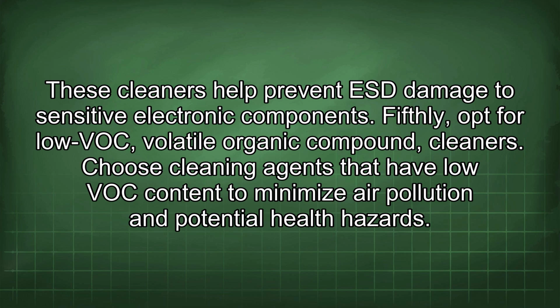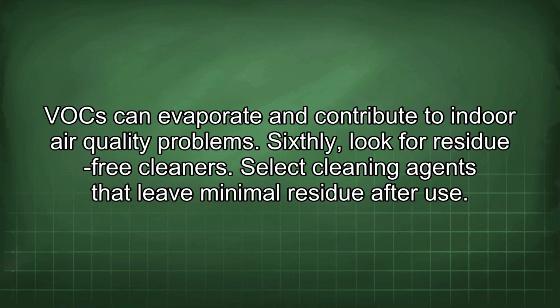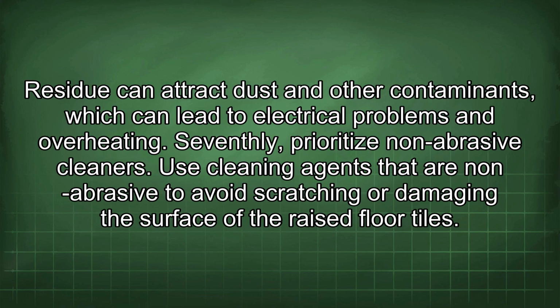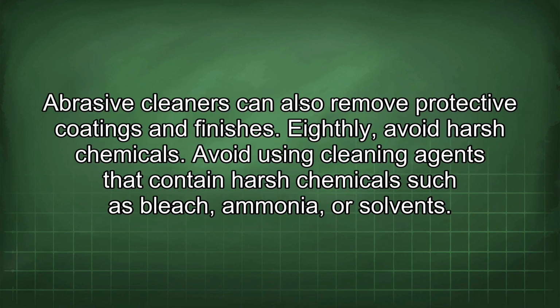Fifthly, opt for low VOC, volatile organic compound, cleaners. Choose cleaning agents that have low VOC content to minimize air pollution and potential health hazards. VOC can evaporate and contribute to indoor air quality problems. Sixthly, look for residue-free cleaners. Select cleaning agents that leave minimal residue after use. Residue can attract dust and other contaminants, which can lead to electrical problems and overheating. Seventhly, prioritize non-abrasive cleaners. Use cleaning agents that are non-abrasive to avoid scratching or damaging the surface of the raised floor tiles. Abrasive cleaners can also remove protective coatings and finishes. Eighthly, avoid harsh chemicals. Avoid using cleaning agents that contain harsh chemicals such as bleach, ammonia, or solvents.